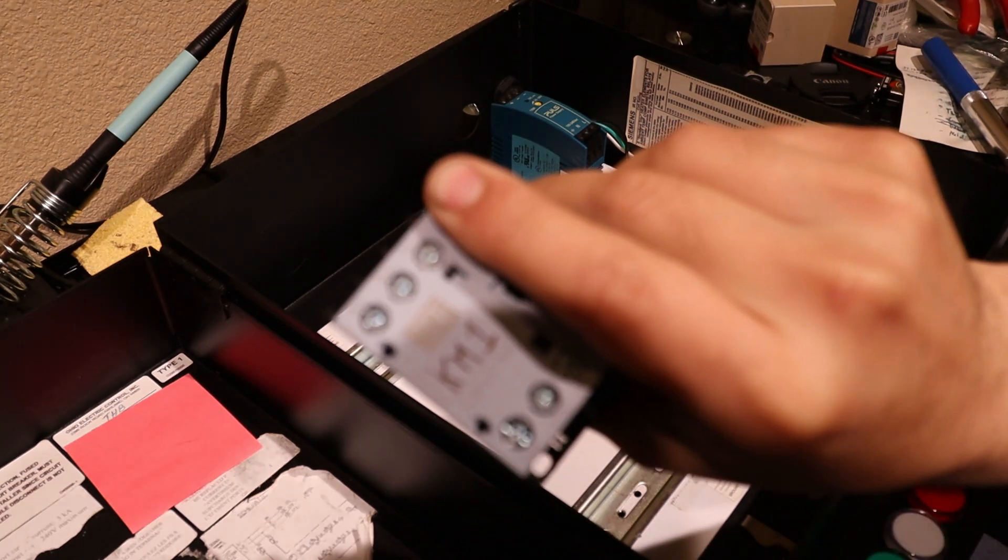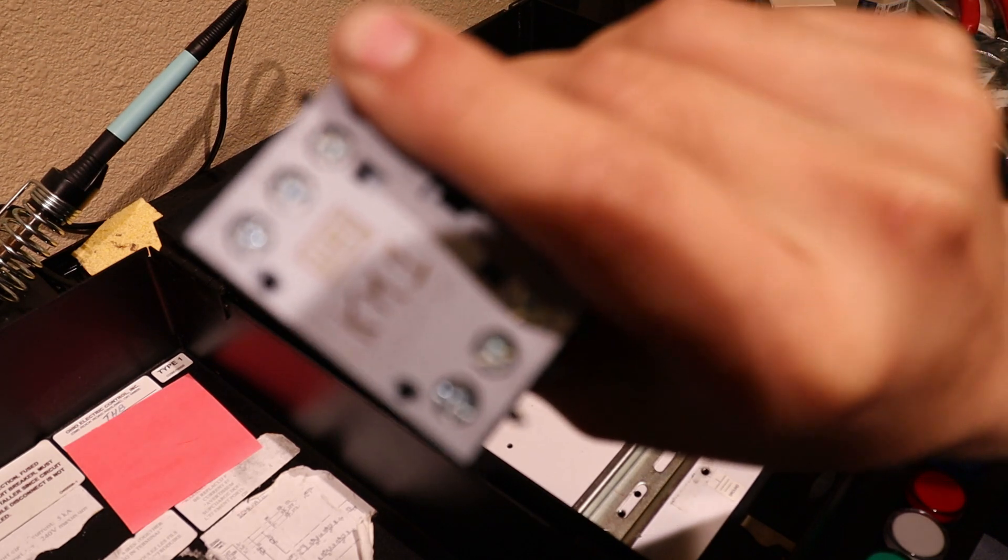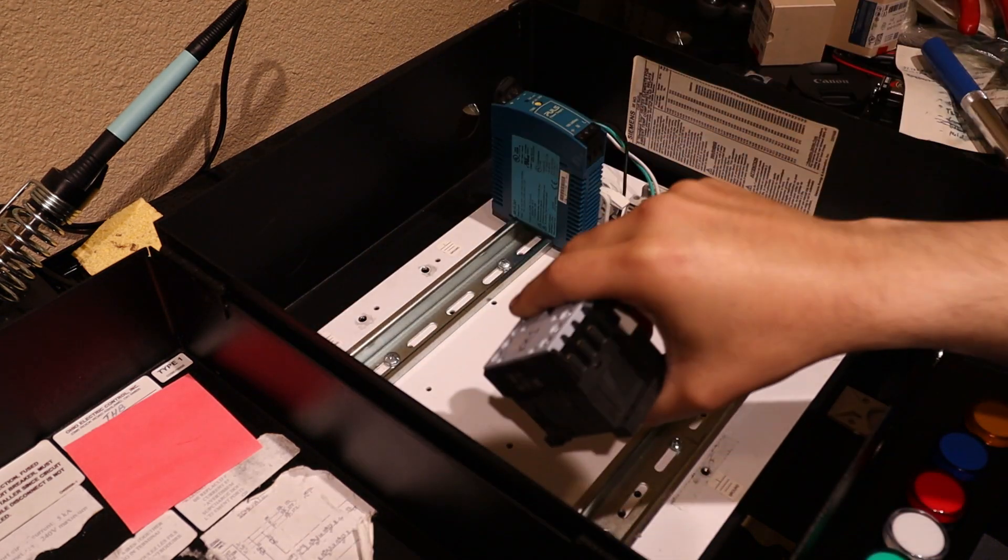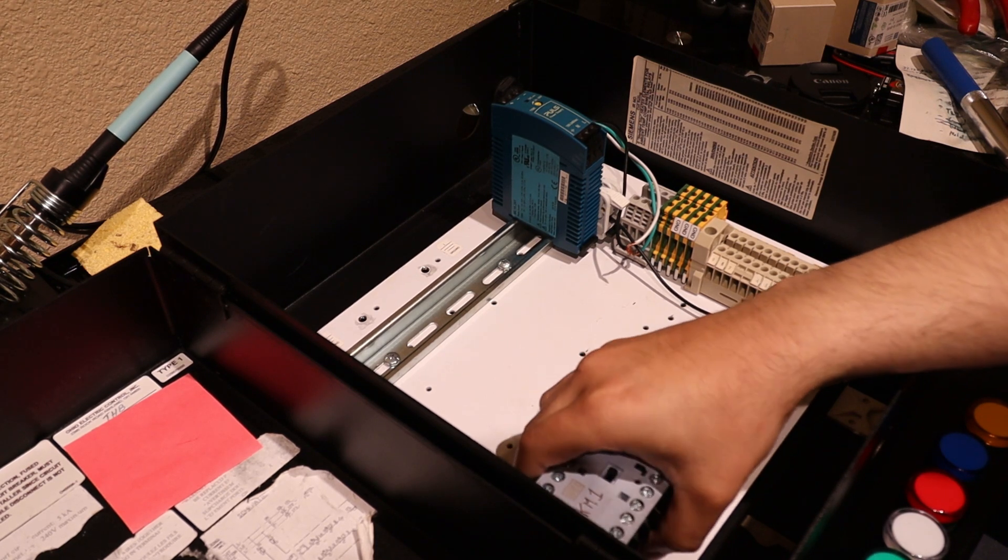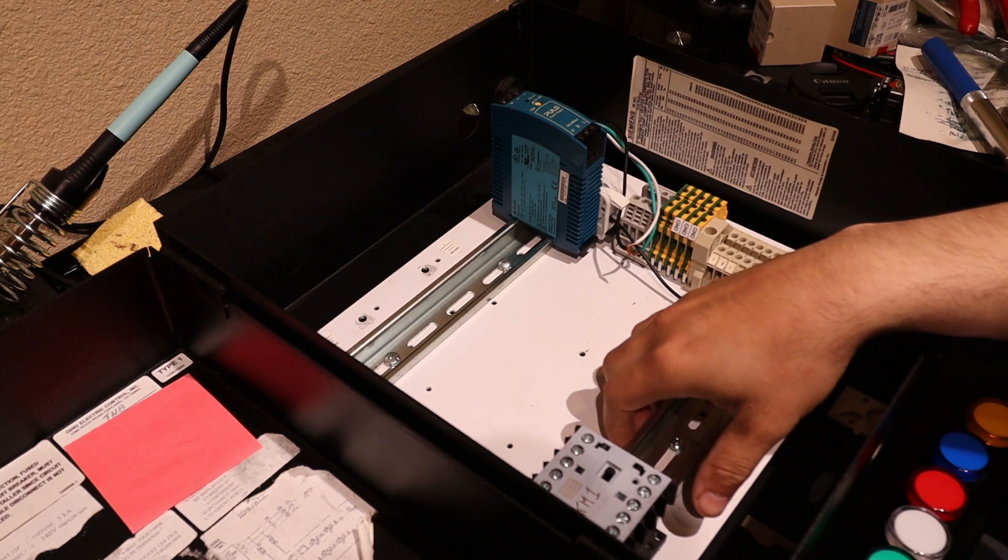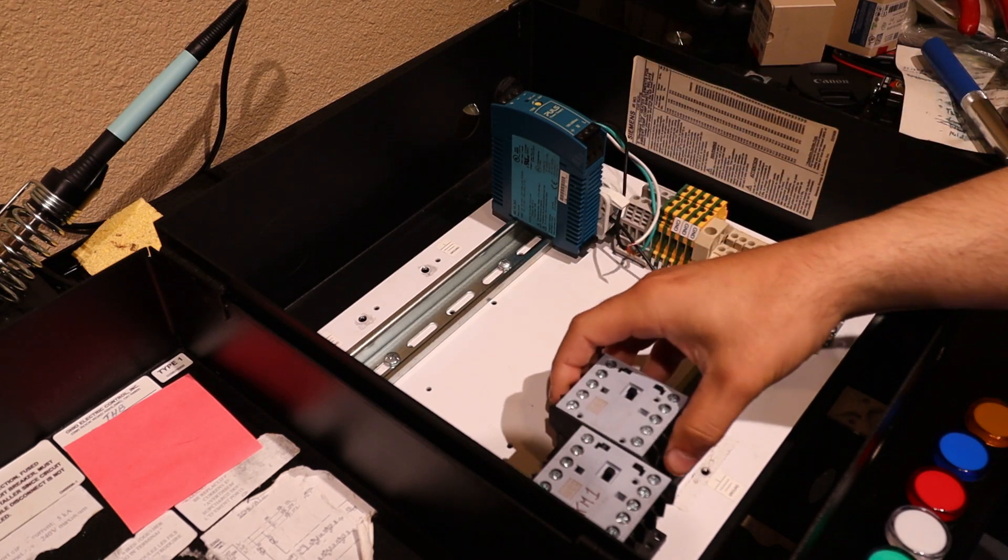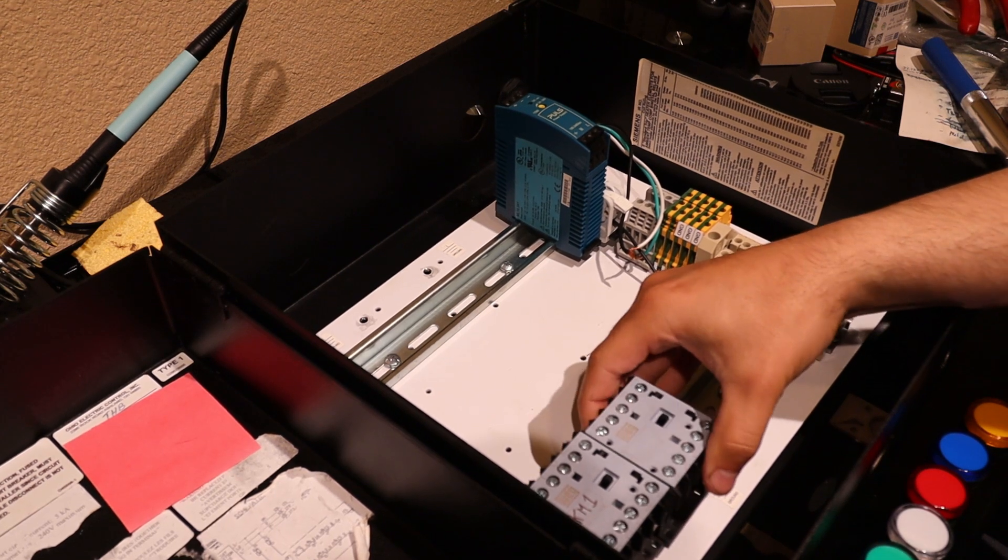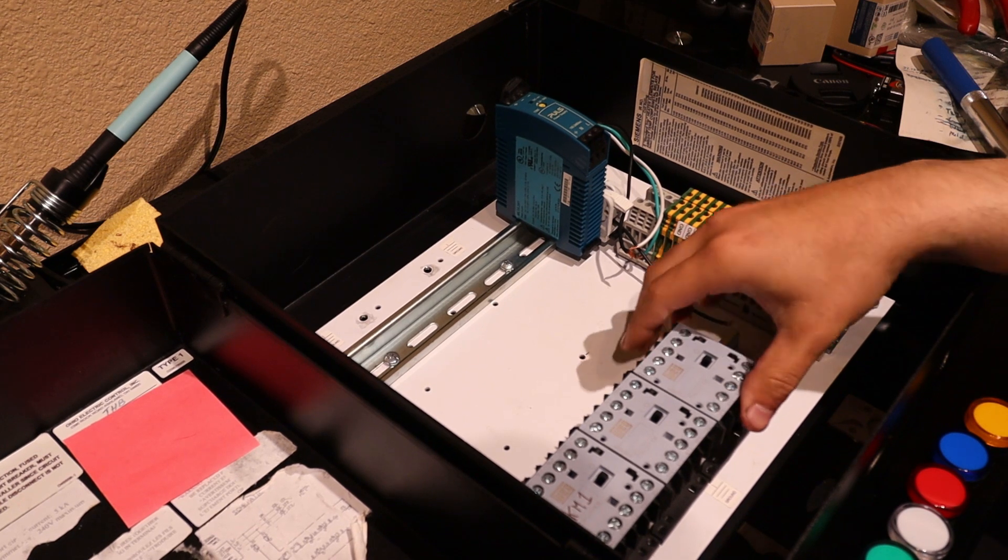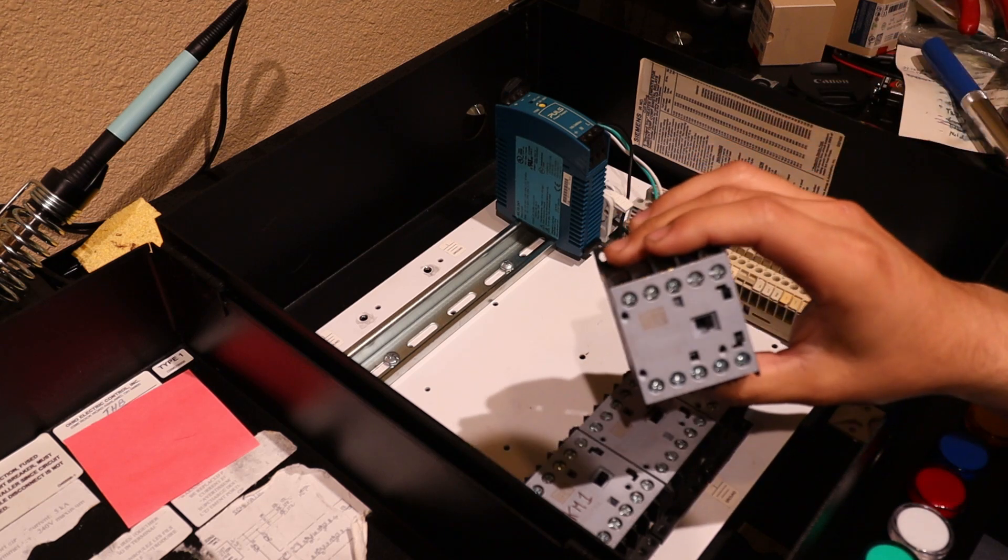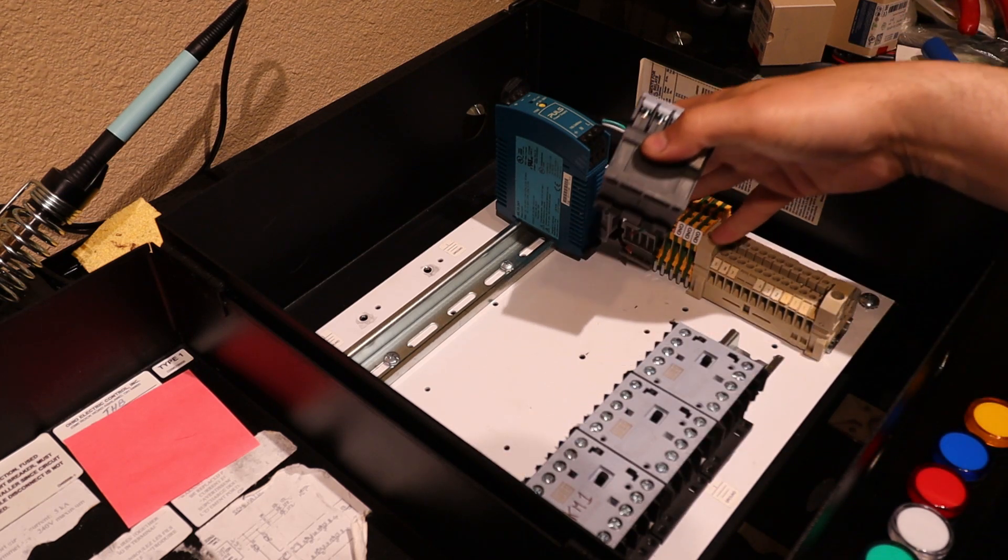You're also going to use these KM1 contactors, also KM2 and KM3 contactors. These three contactors are used to start the main motor in a star-delta starting system, and this is to reduce the inrush current when starting a large motor that normally pulls a very high amount of amperage when starting. The star-delta starting starts it more slowly so it starts with much less inrush current.